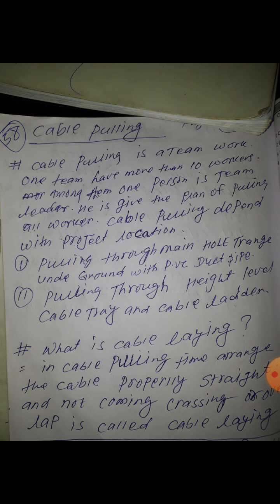If you are pulling a big cable, 240 mm square 4 core, or 185 mm 4 core, like that, you need big manpower. So this is teamwork, not done with one or two people. One team is minimum 10 people and maximum 25-30, as per the cable size and as per the cable length, how far it is going from the electrical room to the LT room or substation.